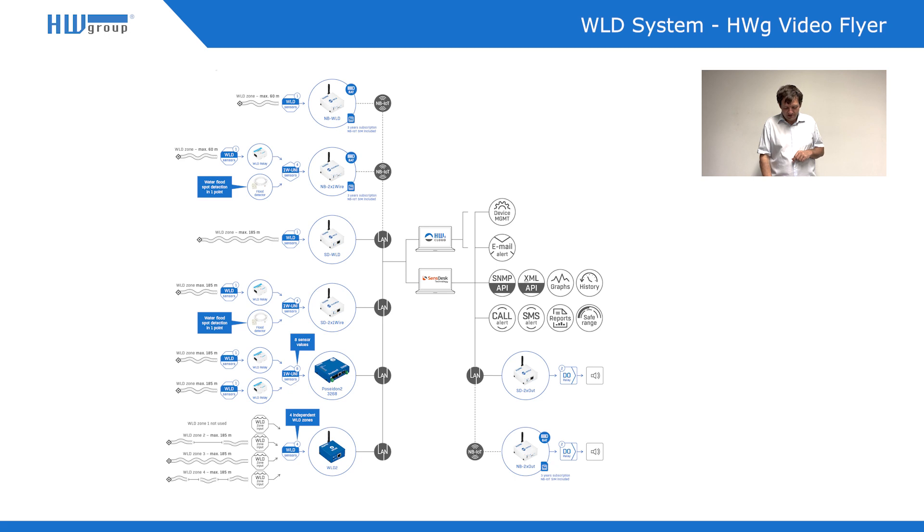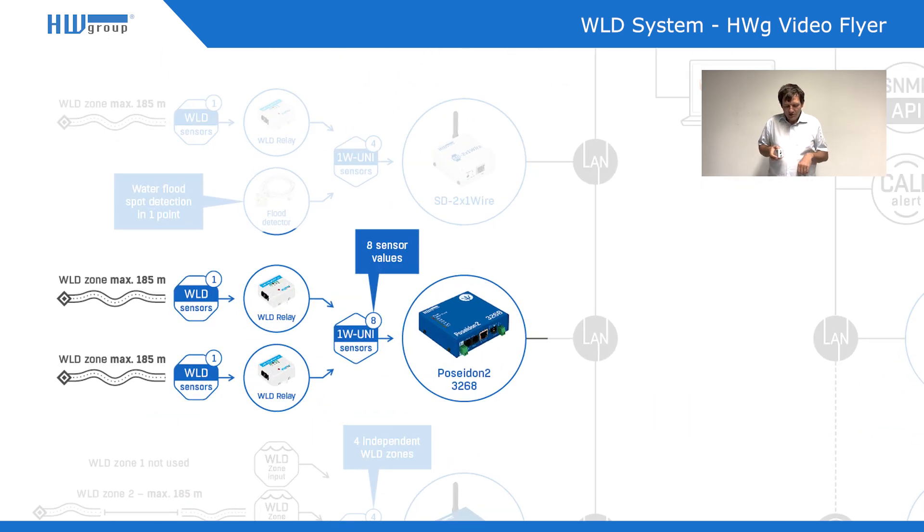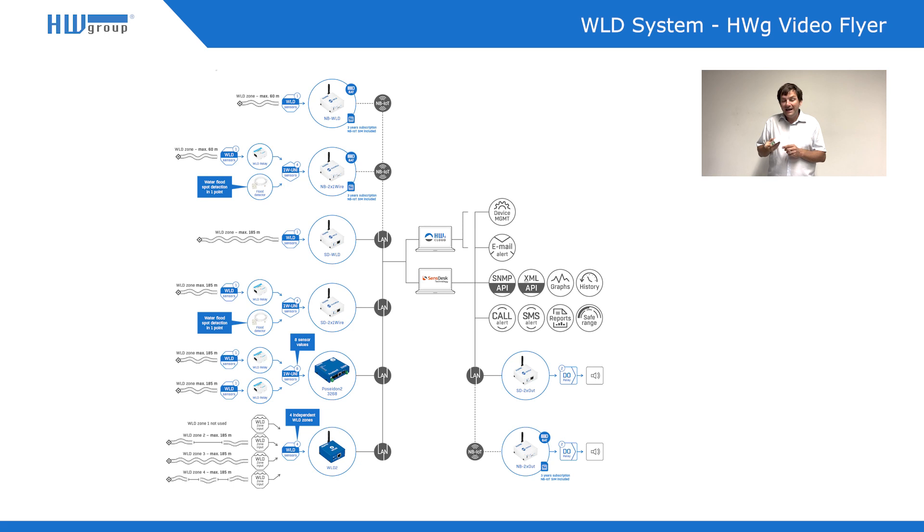This sensor cable can be connected as a zone to four different devices. The first one is called WLD Relay. This box is two-in-one: it can be connected to any ARES or STE device simply by RJ11 cable and doesn't need anything else. Or it can be connected to any third-party product, sensor system, PLC, or security system, because there is a relay output which simply signals whether there is a water alarm or not. It requires external 12V power. We have a separate video about this product.